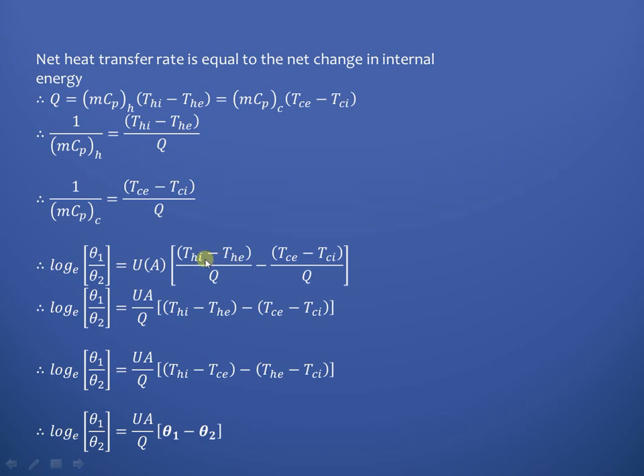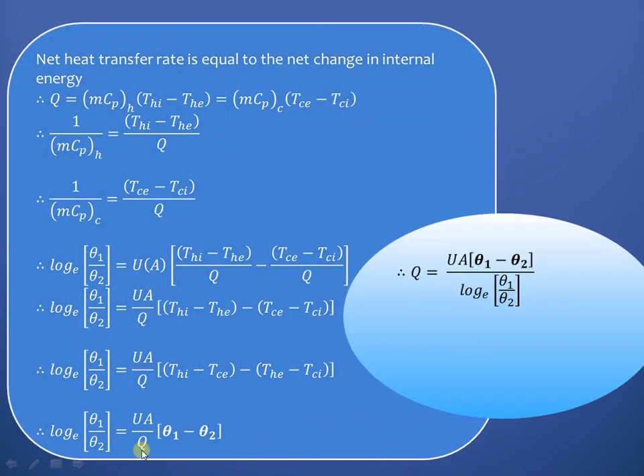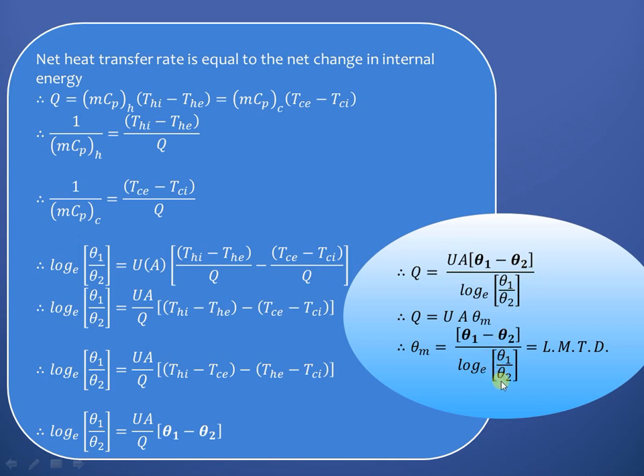Rearranging the bracketed terms: (T_hi - T_ce) - (T_he - T_ci), which is theta_1 minus theta_2. Therefore Q = U·A·(theta_1 - theta_2) / log(theta_1/theta_2). The term (theta_1 - theta_2) / log(theta_1/theta_2) is defined as the log mean temperature difference, or LMTD.